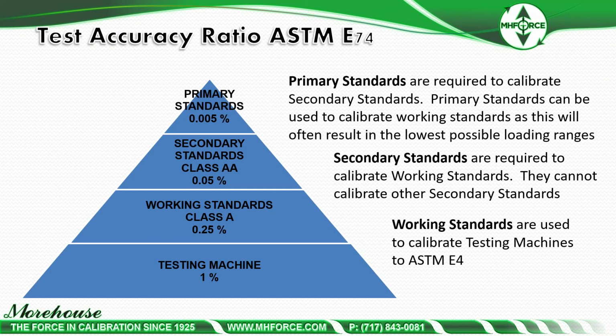Test accuracy ratio, this term should be dead. It lives on in E74 because it is a standard, and we as a committee and ASTM as a standards organization can control what happens here. So you have primary standards at the top. They're required to calibrate secondary standards. Primary standards can be used to calibrate working standards, as this will often result in the lowest possible loading range. Secondary standards are required to calibrate working standards. They cannot calibrate other secondary standards, and working standards are used to calibrate the testing machine.